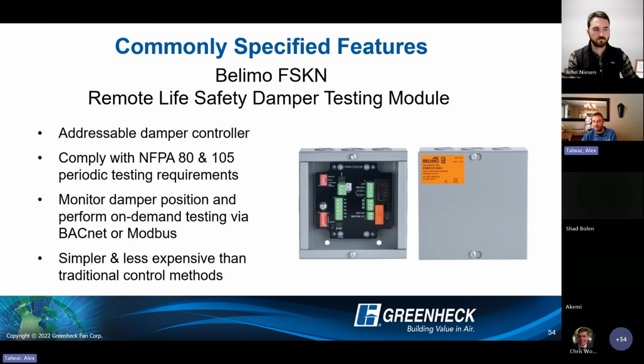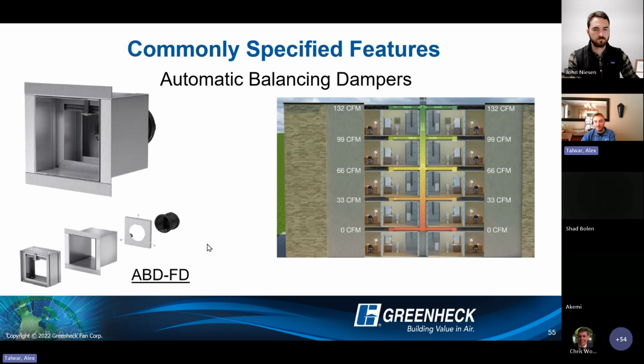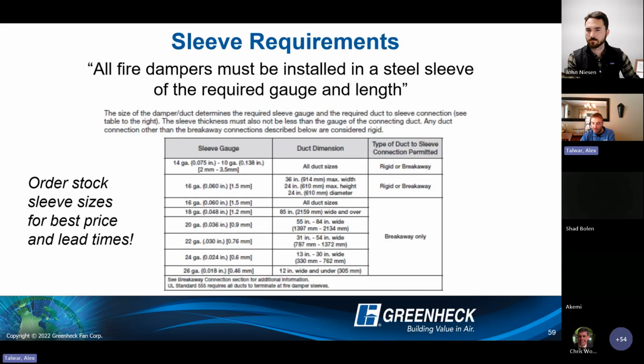So again, we're just trying to make more options available from the factory and make it easier to get everything in one package. We also have these automatic balancing dampers that we can provide with fire dampers. So it's kind of set it and forget it in terms of the airflow set point. It's got a little leaf spring and blade on the back that will fluctuate with the change in pressure and maintain a constant CFM through that opening. All right, now I'm really going to start flying through here.